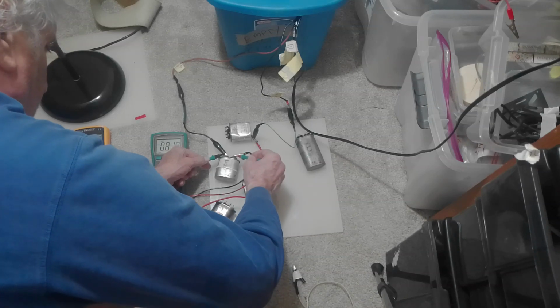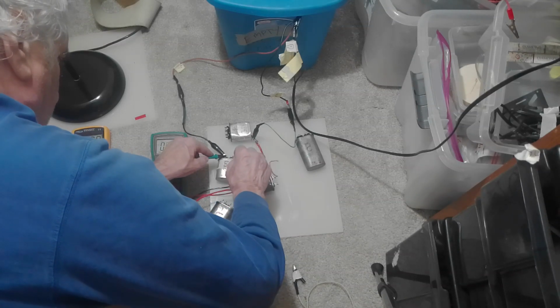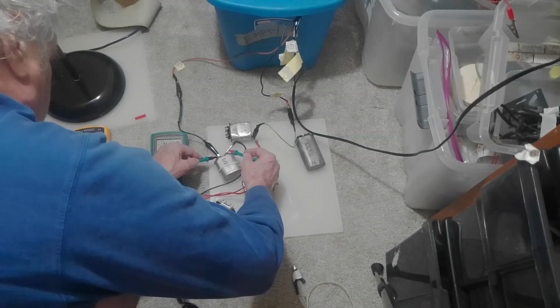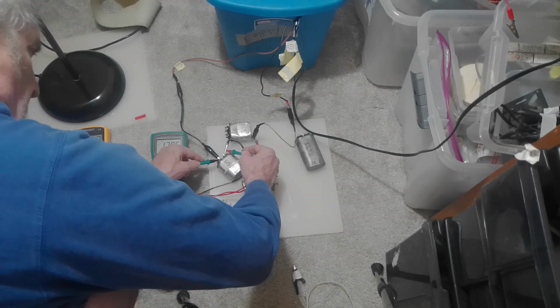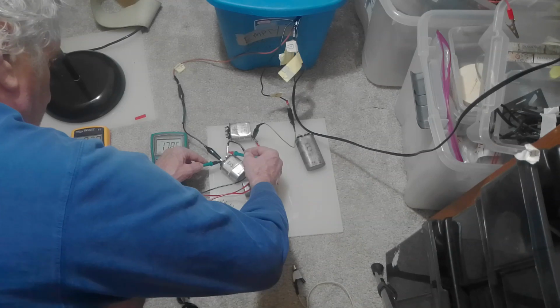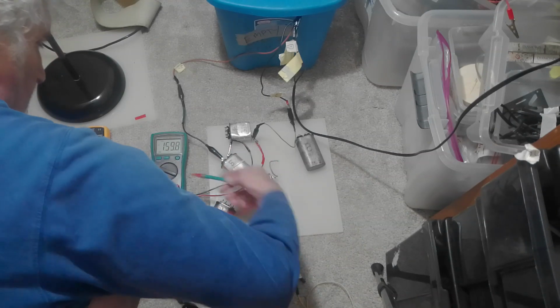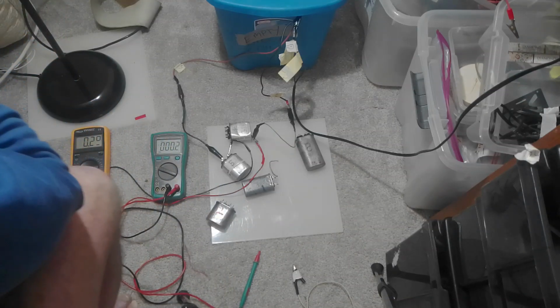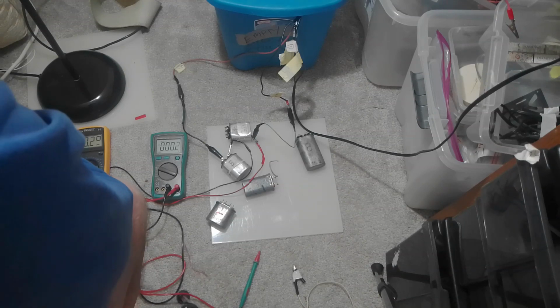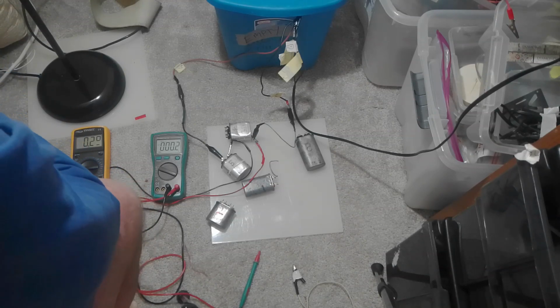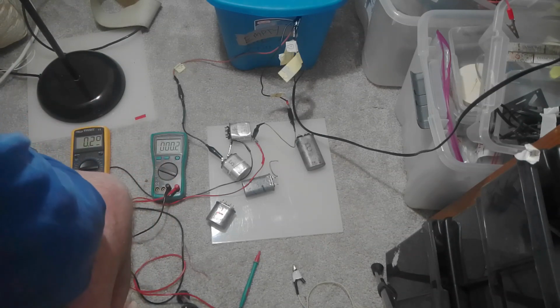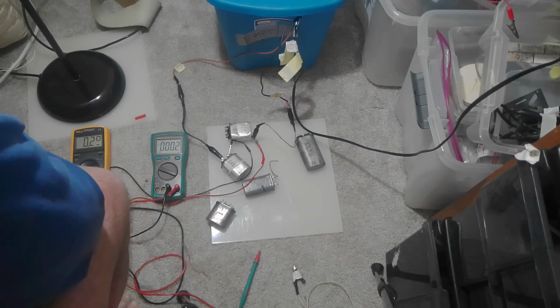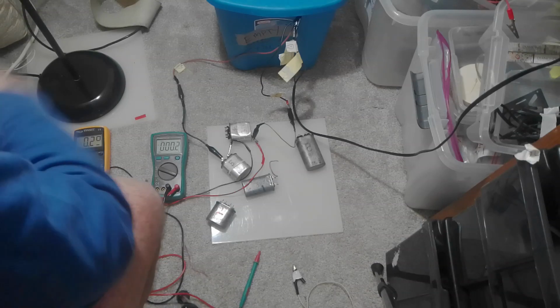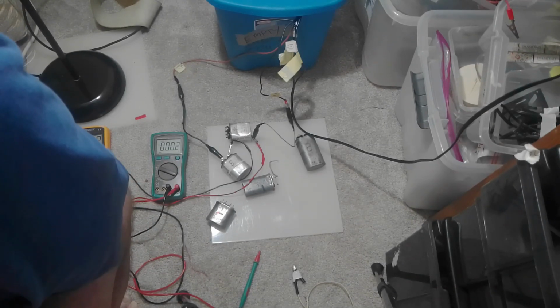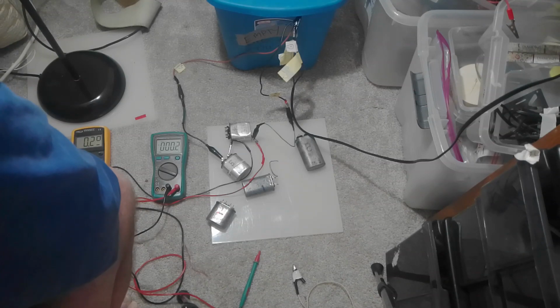and the voltage, wow, what's going on? 178 volts across the run cap. So this is not watts, this is volts, amps, reactive, VARs. This is what's circulating through that run cap phase. So this is what you get to play with, this power. And this is what's within the run cap phase. And you can change what you have.